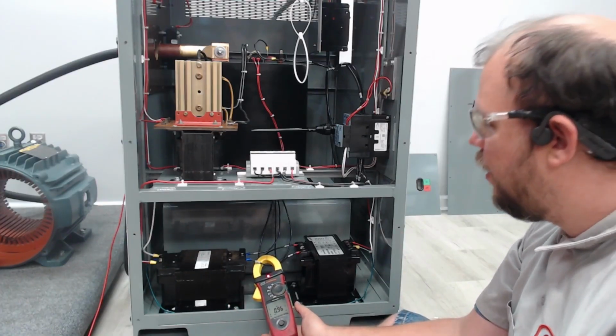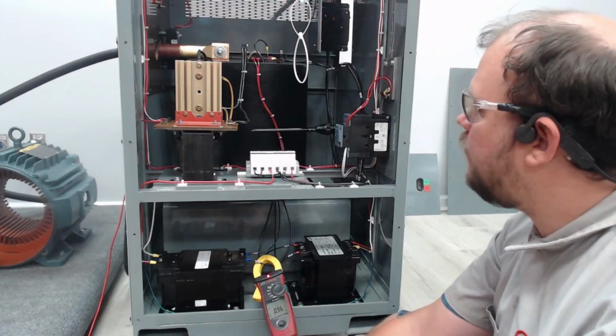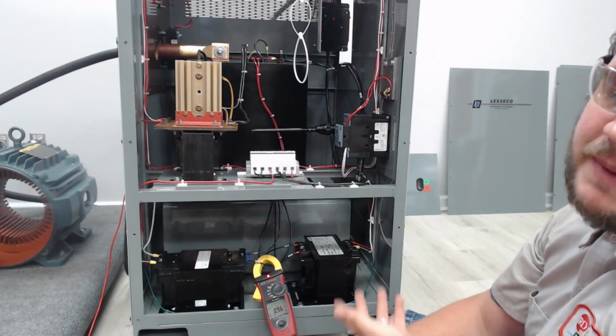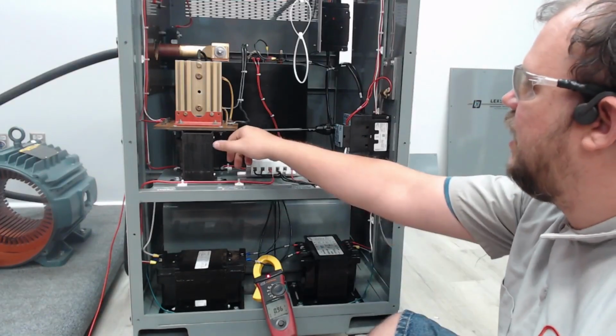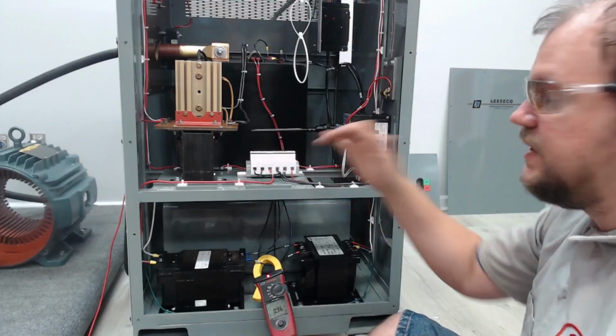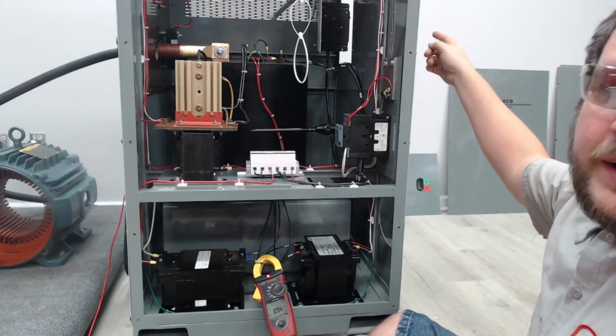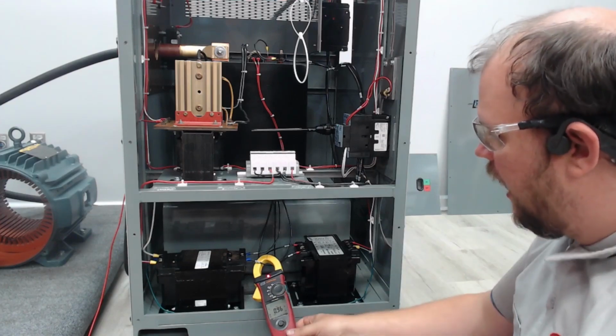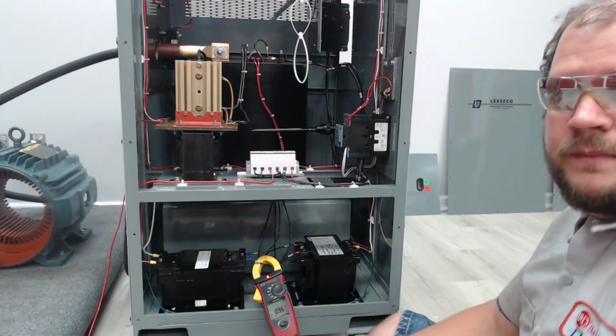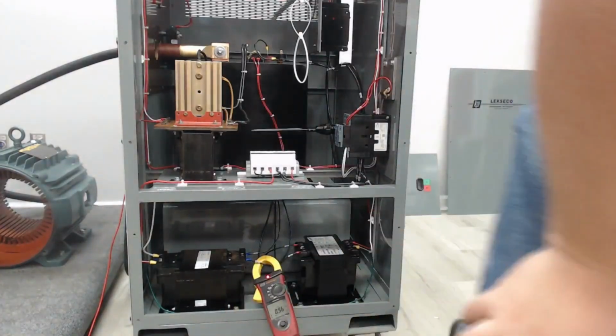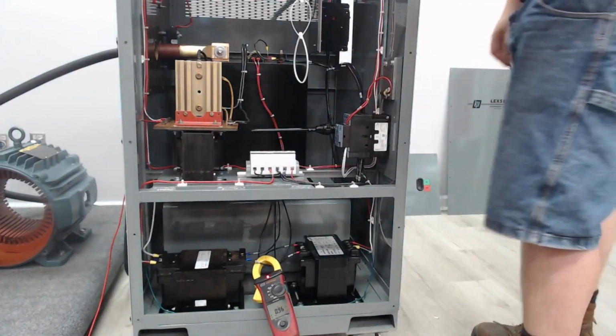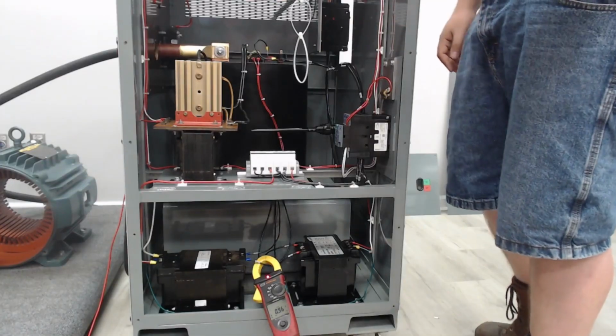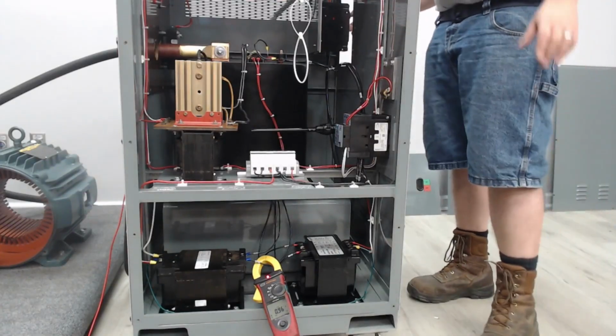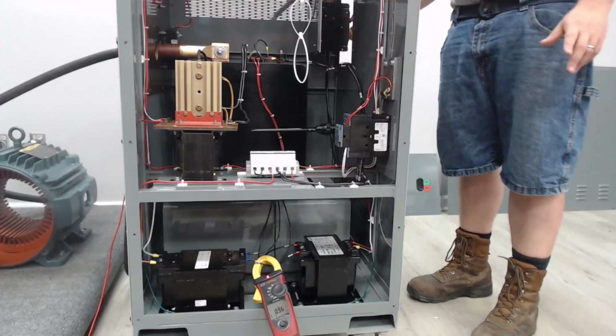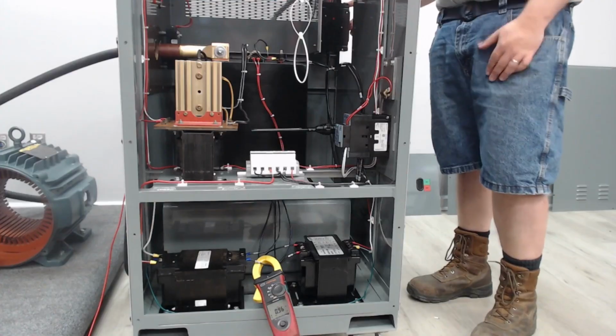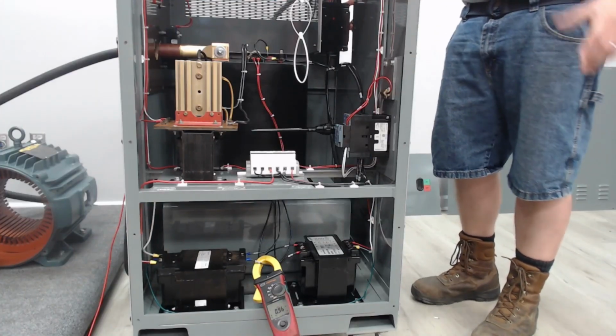So now that I know what the max is on a normal ramp up, in case you're blowing fuses, you may not know this, but you can at least check that your fuse number is higher than that number. What I'm going to do now is go over to the breaker and turn it on and off a couple times. We're going to see if I can get a higher inrush current going on through the initial turn on of the unit. Once again, if you're blowing fuses, this is going to cost you a fuse probably every time you do this. Buy a box of 10, buy a box of 20. If you're a professional, consider subbing in a breaker so you're not having to burn through fuses.